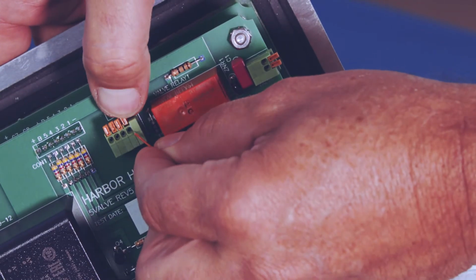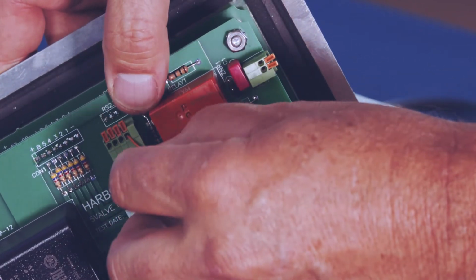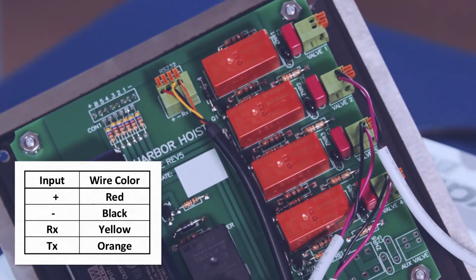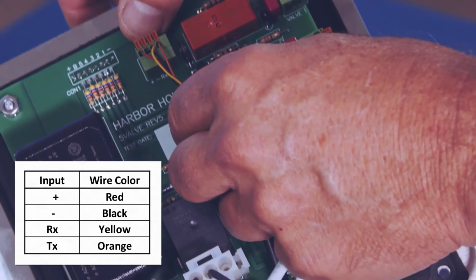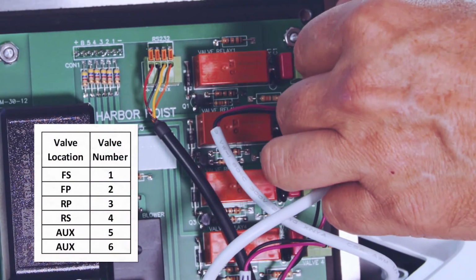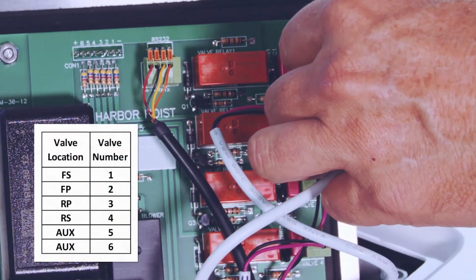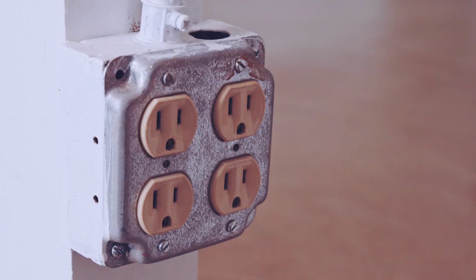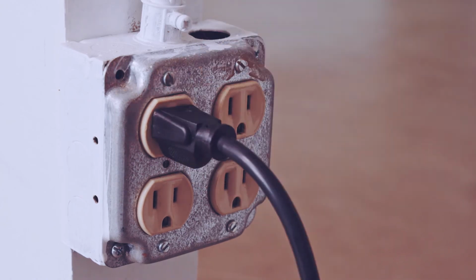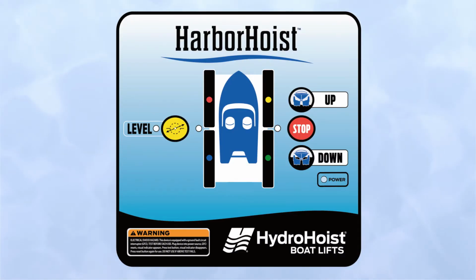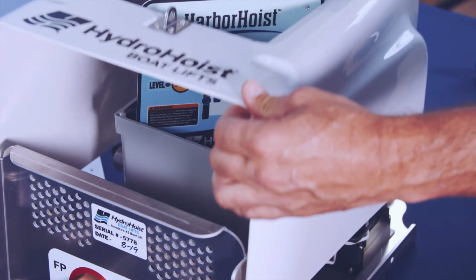Insert wire leads for the level sensor and valves by pushing down on the orange lever on the connector. Make sure they are secure by tugging on them. Power up the control and verify it operates properly. Reassemble the housing and front plate.